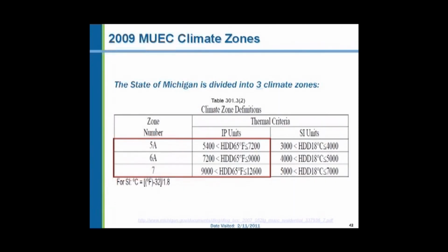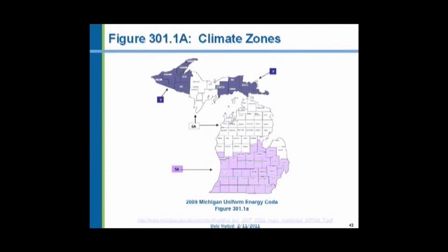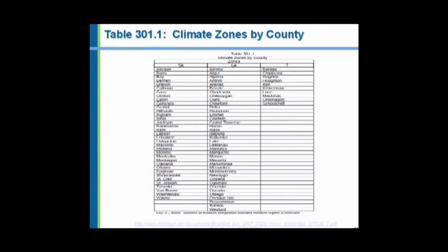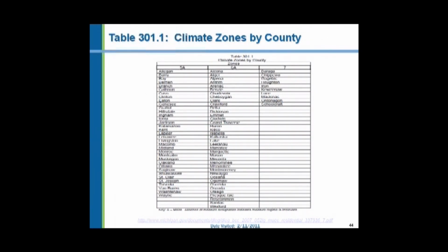Here are the tabulated data. 5A, heating degree days between 5,400 and 7,200. 6A is between 7,200 and 9,000. 7 is between 9,000 and 12,600 heating degree days. And here is a map of the state of Michigan, taken from the Michigan Energy website. And there's our little anomaly in the Upper Peninsula, but look at this. Right in this part of the state, instead of going from north to south to change climate zones, you go from east to west, right here, these 2 counties. That's a little anomaly that you should be aware of. And here they are enumerated. You can actually see printed in legible form which county is in which climate zone.